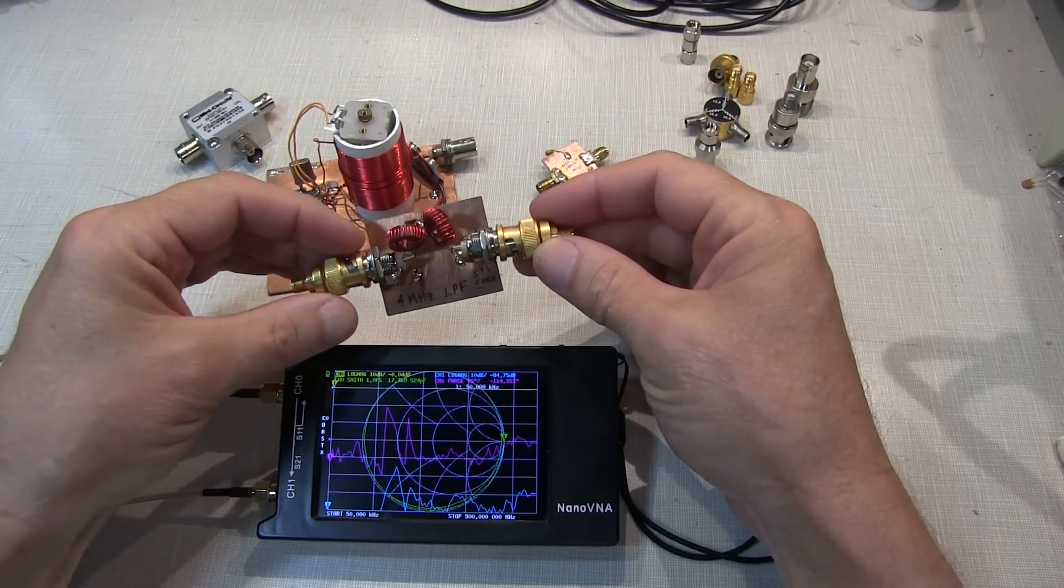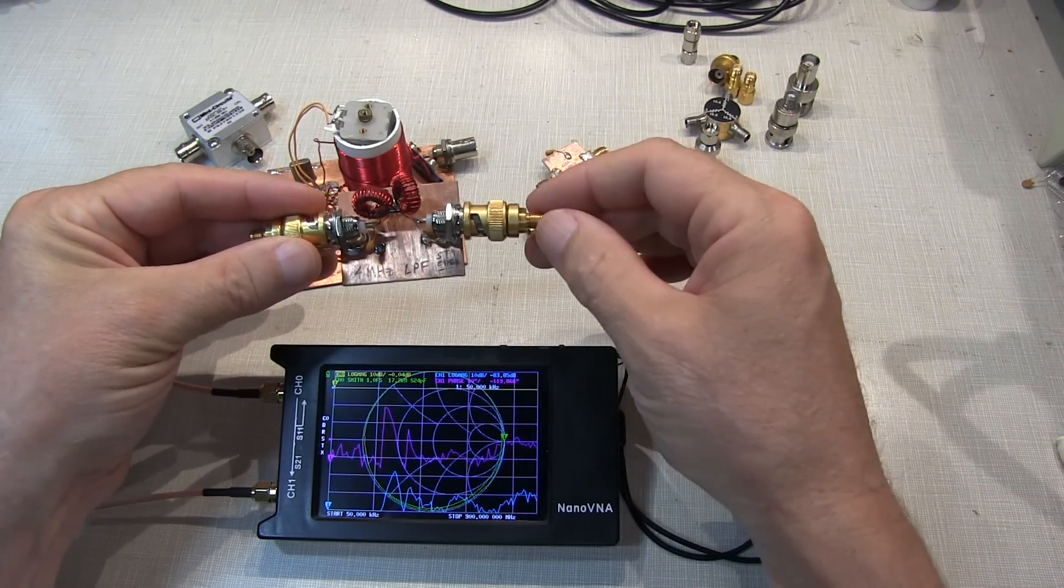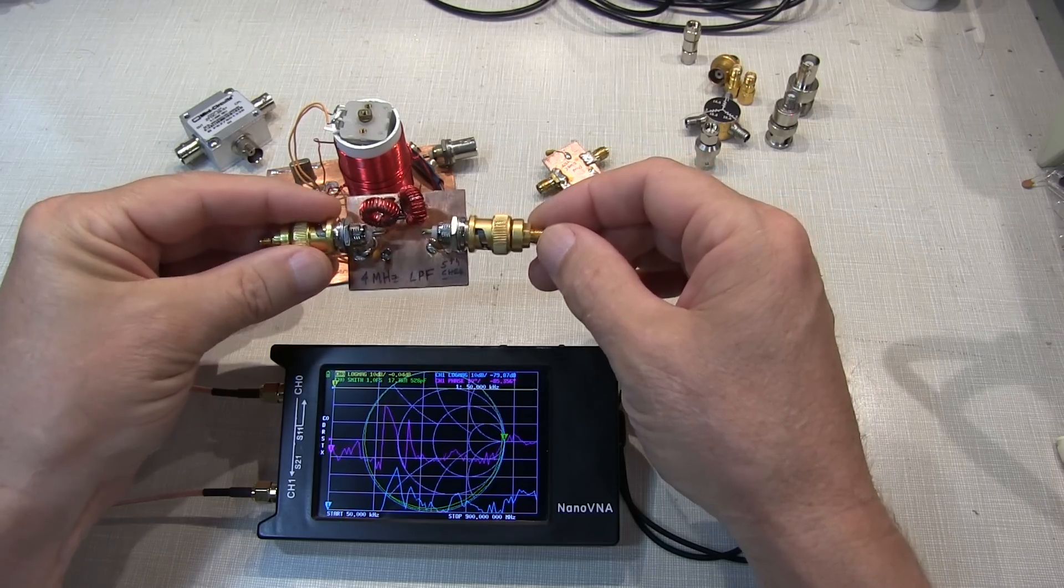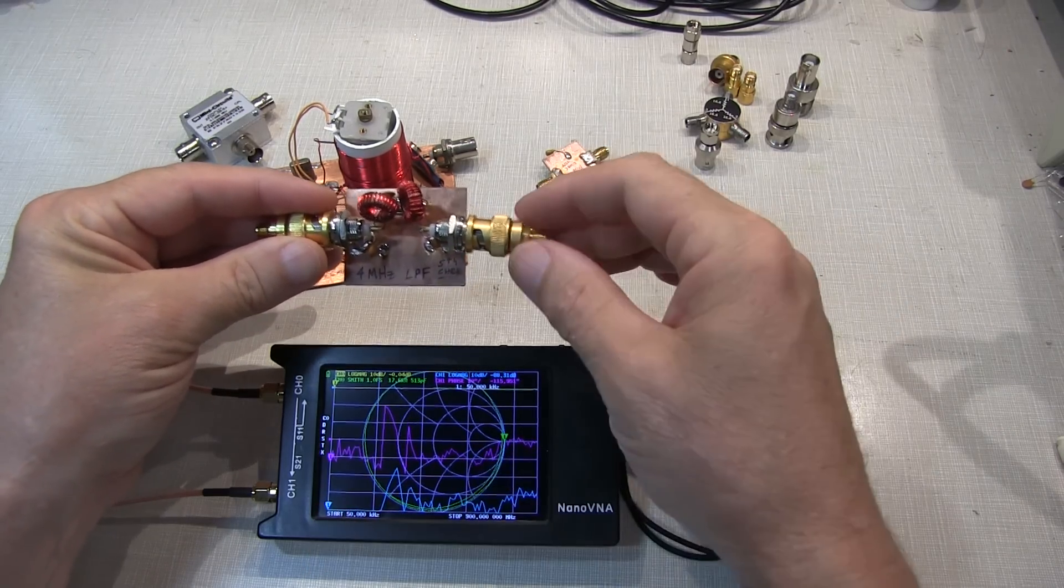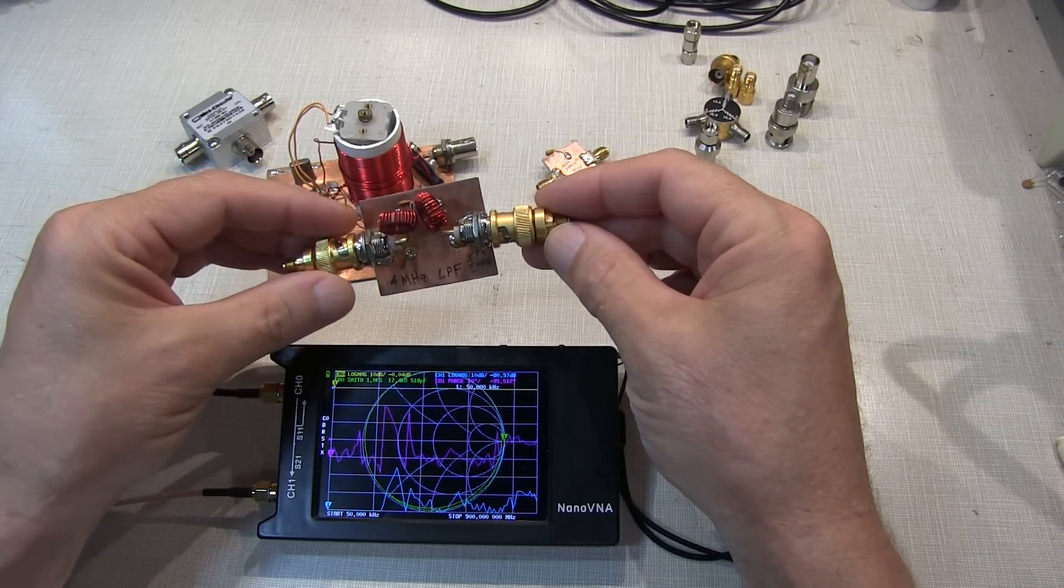The process will be quite similar to the previous video that showed how to measure an antenna. We first select which traces we want to have displayed, configure the source frequency range we want to measure over, then calibrate the device, and then go measure our part. So let's get started.